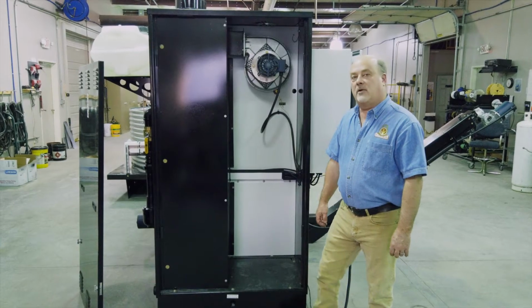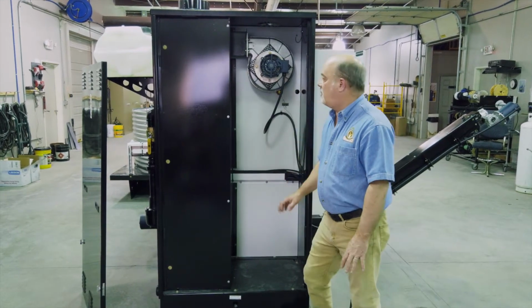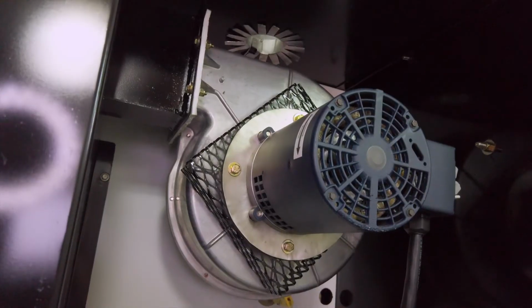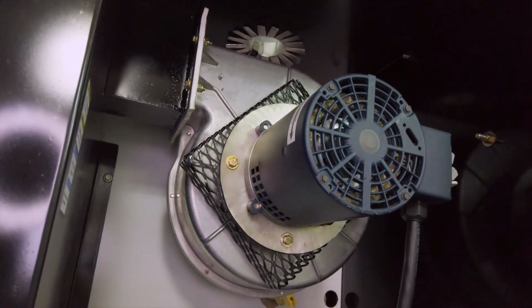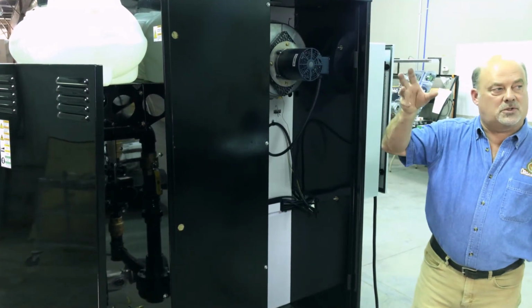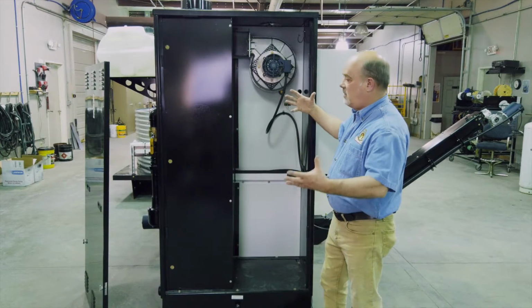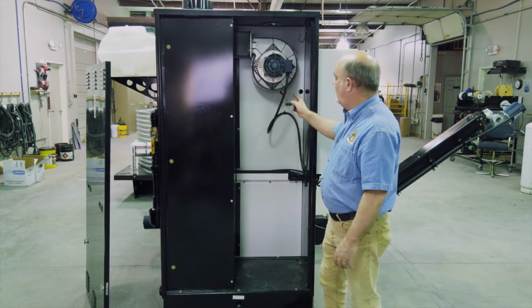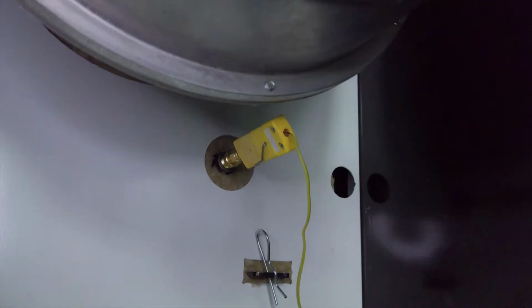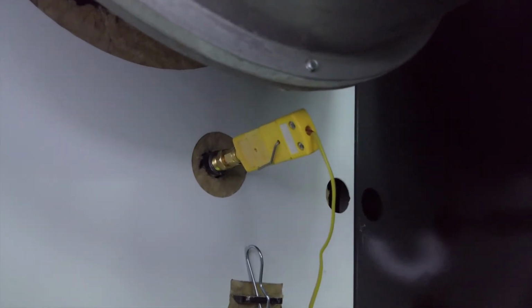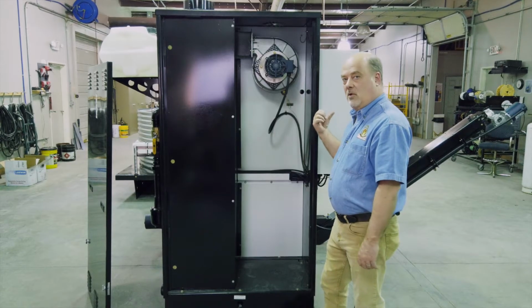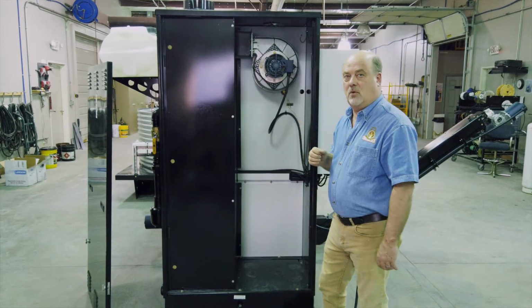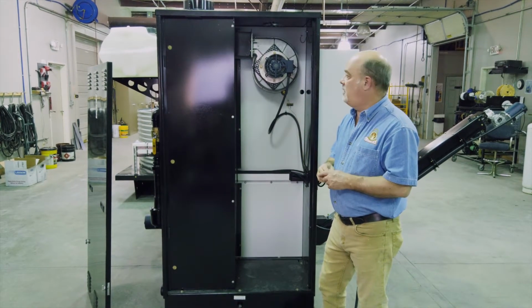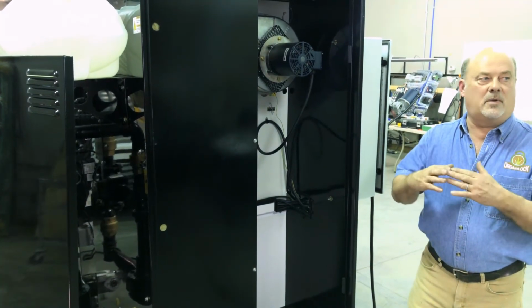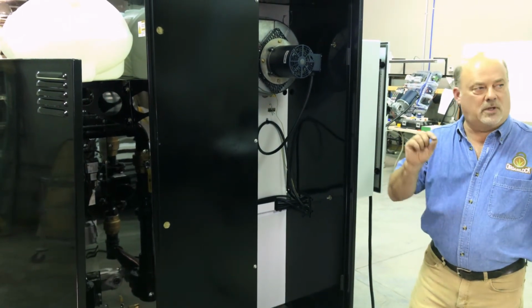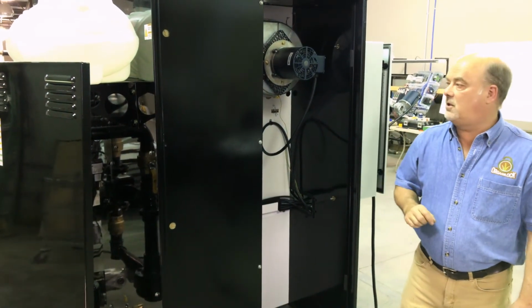All right, here we are on the final side of the machine, where we have a couple of components to talk about. We have the induced draft fan. What that means is it's pulling the gases through the machine, which makes it very safe to make sure everything's always being drawn in. We have a thermocouple up inside here where we measure the temperature of the flue gas. If it gets too hot, the computer lets you know. It actually turns the fuel off until it turns back down a few degrees. It'll let it cycle and let you keep running, but every time it hits that max temperature, you get the message. It's telling you clean your machine.